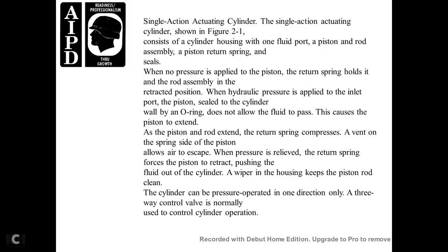Single-Action Actuating Cylinder. The single-action actuating cylinder shown in figure 2-1 consists of a cylinder housing with one fluid port. With no pressure applied, the piston return spring holds the rod assembly in the retracted position. When hydraulic pressure is applied at the inlet port, the piston — sealed against the cylinder wall by an O-ring — is caused to extend. The return spring compresses on the rod side. The spring side of the piston allows air to escape through a vent. When pressure is relieved, the return spring forces the piston to retract, pushing the fluid out of the cylinder and causing the piston and rod to retract.